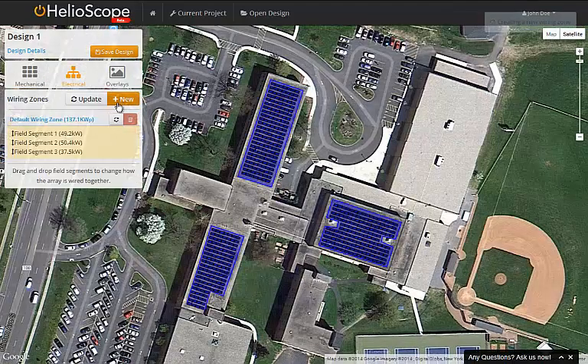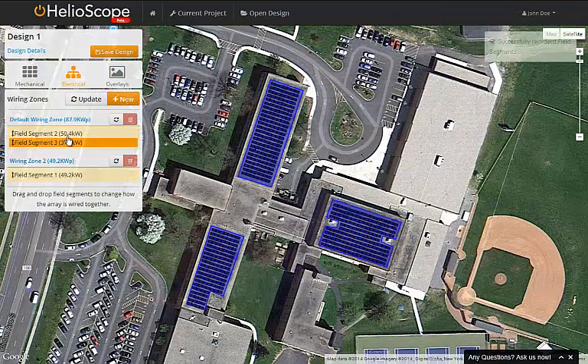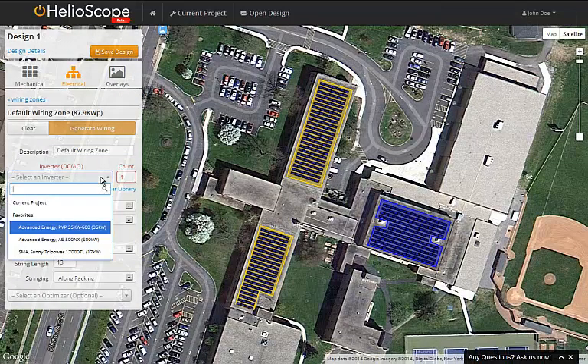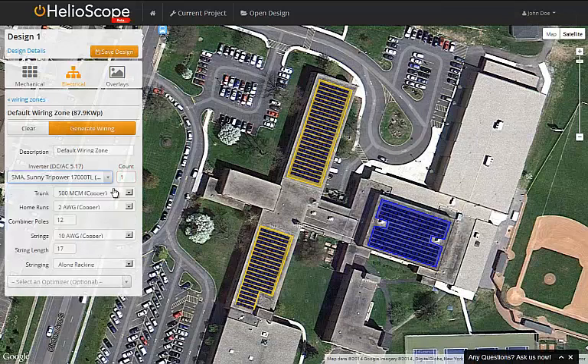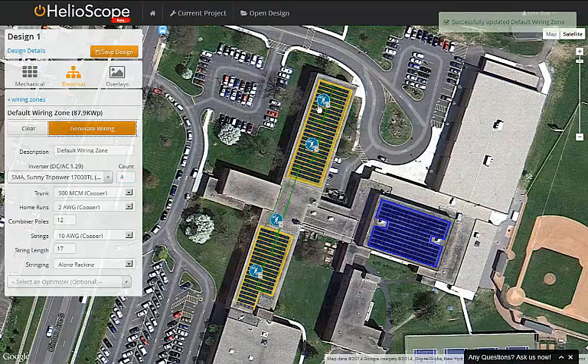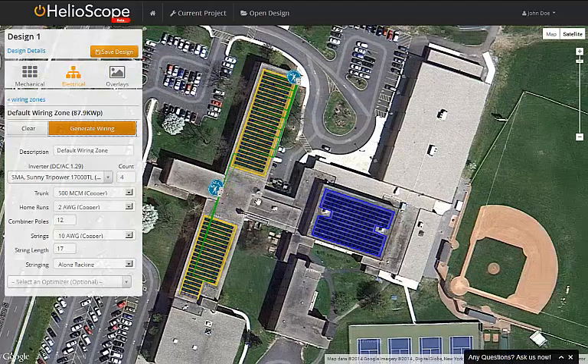In this case, I'm going to break the system up into two wiring zones — one for the western part of the roof with two field segments, and the other for the east. In the electrical design, I choose the inverter and quantity, leave the conductor defaults, and hit generate wire. The modules are automatically assigned to strings, and the wires connect each string to each inverter. I can now move around the inverters, and as I do, it's going to be automatically rerouting the conductors from each string to each inverter.